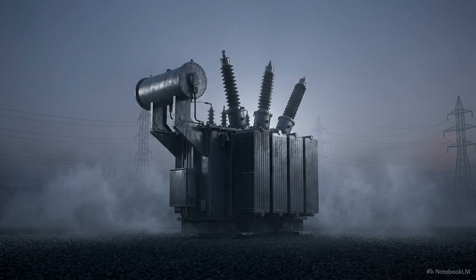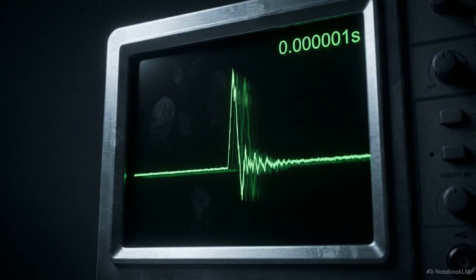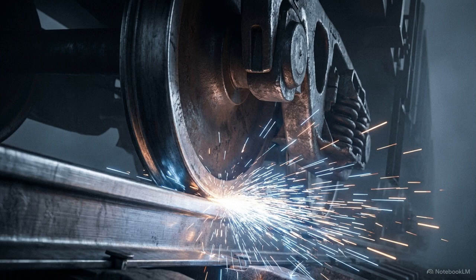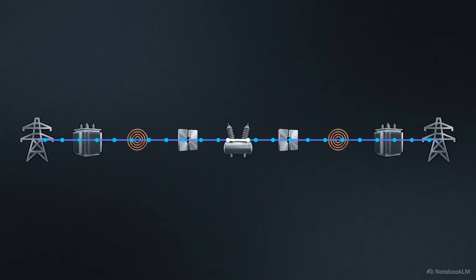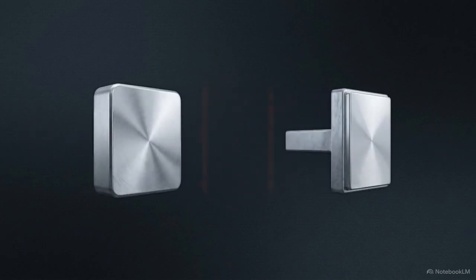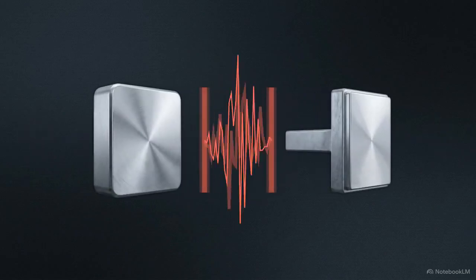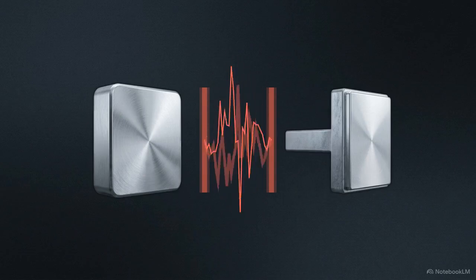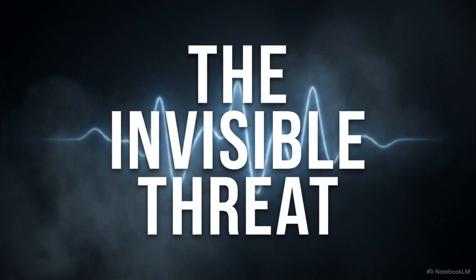It looks like the breaker has won, but the true danger is just waking up in the invisible microsecond window that follows. The sudden interruption of a massive fault current acts like slamming the brakes on a freight train. It leaves huge amounts of inductive and capacitive energy trapped in the surrounding network. That trapped energy immediately rebounds. The instant the current dies, a high-frequency voltage violently appears across the open breaker terminals. This is Transient Recovery Voltage, or TRV.